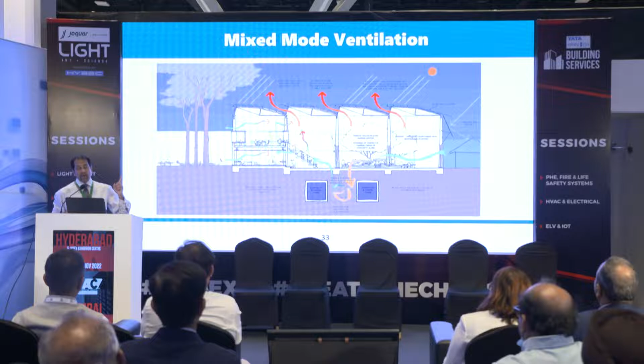Now things are changing. We see the whole facade opening up — we take the outside air in and run with natural cooling. If there's a problem, run a little fan. If there's still a problem, maybe inject 10% cold air and circulate that. And if you really have a problem, which is only for 2 to 3 months a year, that's where you get into fully air-conditioned operations. Why? Because it cuts down your energy bill, and that brings you closer to net zero operations.